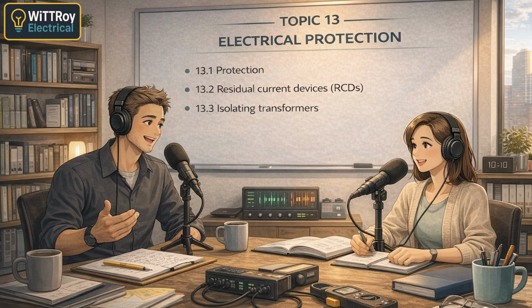Now, how does an RCD actually detect a fault? It measures current to earth? Close. It compares current in the active and the neutral. Oh, right, they should be the same. Yes. Under normal conditions, current flowing out equals current flowing back. And if they're not equal, something's leaking. Exactly. That imbalance indicates leakage current. Usually through a person or faulty insulation. Correct. When that imbalance exceeds the rated value, the RCD trips.